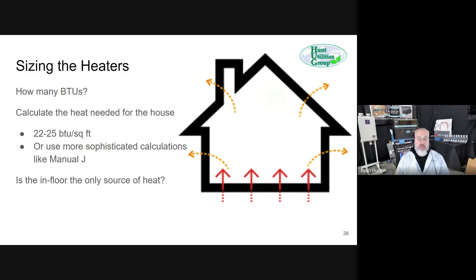So we can help you figure that out. Generally, we'll do a rough estimate first. For typical new construction, 20 to 25 BTUs per square foot is what we're going to calculate as the first estimate. You can use more sophisticated calculations like Manual J, a process that heating and cooling contractors will typically use. And we can walk you through something like that also if needed, or recommend someone to help with that.